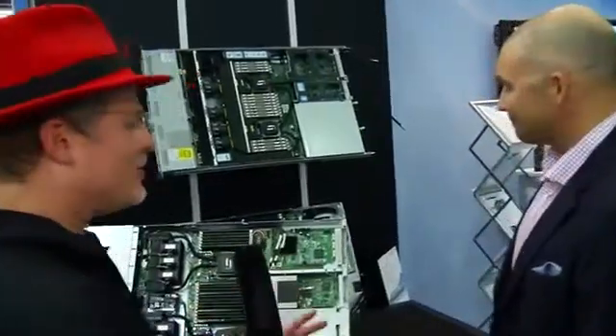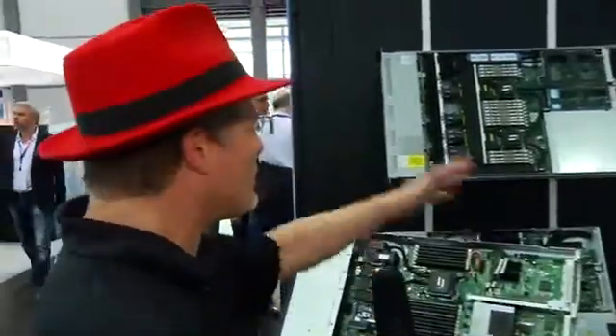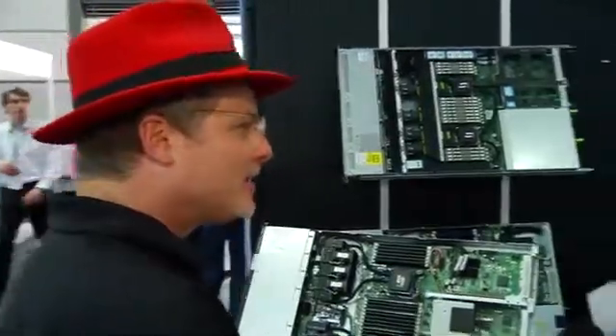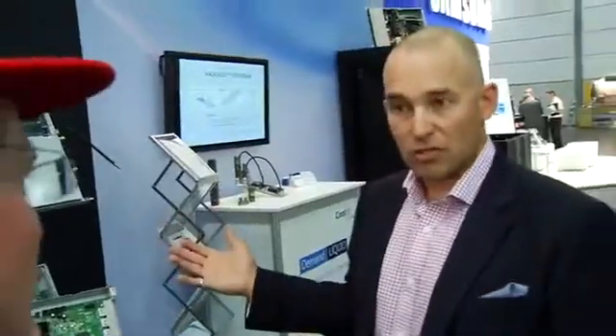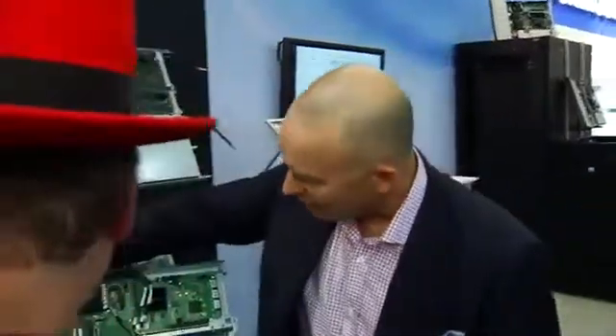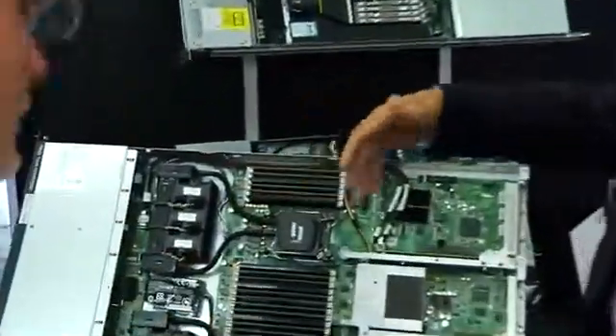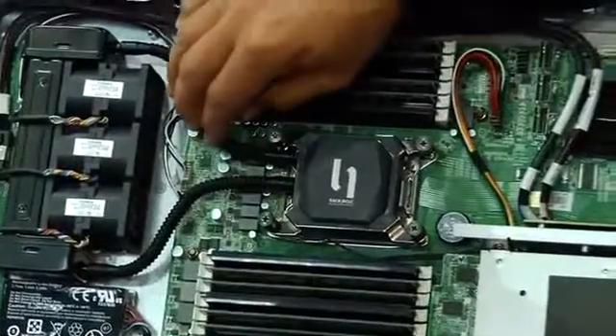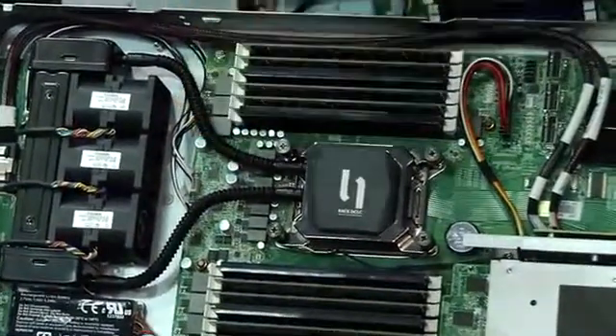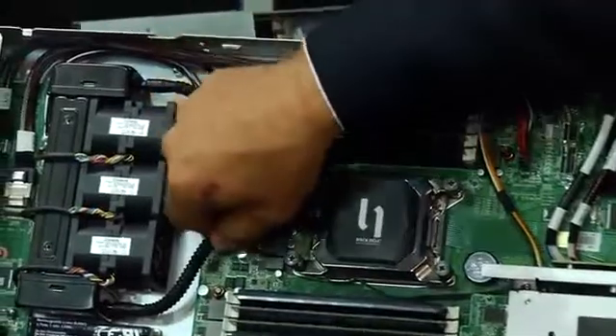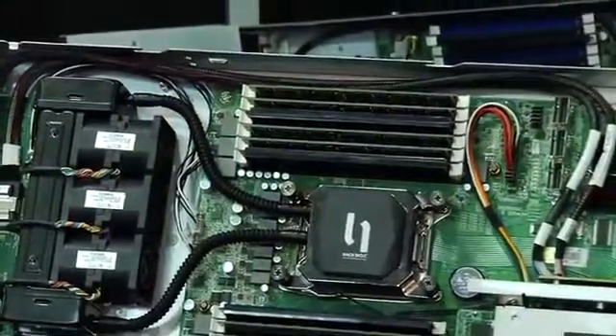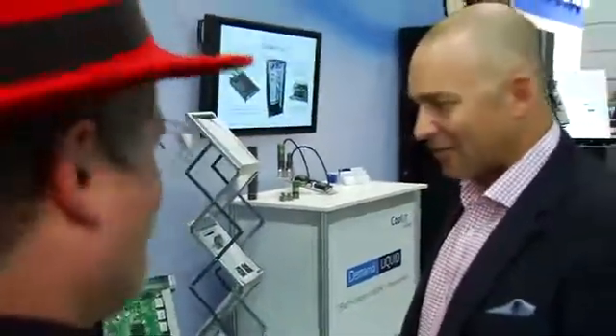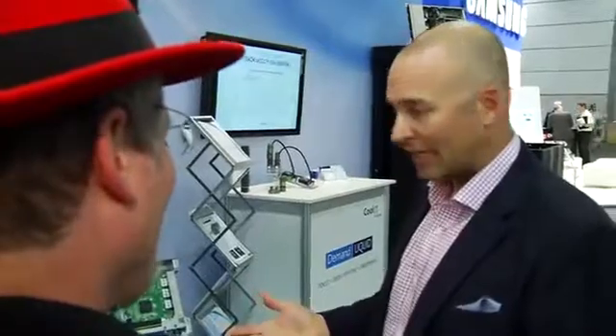So the thing about liquid cooling is pipes leak. What have you done to mitigate that? Well, we've done our best to ensure we're using proven technology. We have over 1 million of these systems in use today. The joining technology is a very robust FEP tubing, which has very low water vapor transmission. It's incredibly durable - quite hard if you try to bend or squish it, very difficult to do so. So there's little risk of damage or abuse resulting in a leak.